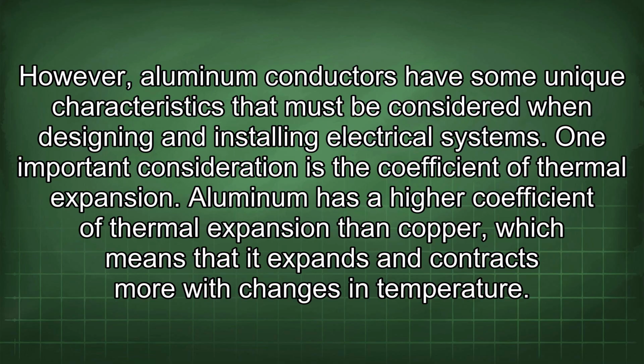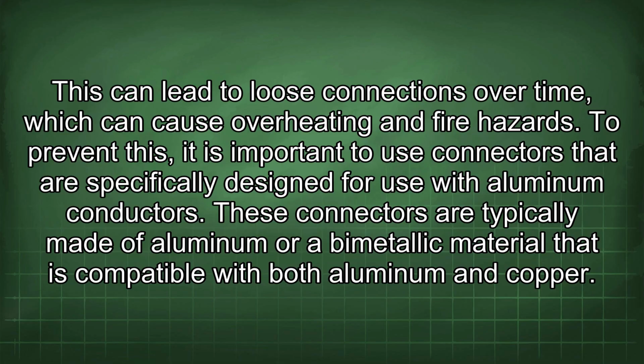One important consideration is the coefficient of thermal expansion. Aluminum has a higher coefficient of thermal expansion than copper, which means that it expands and contracts more with changes in temperature. This can lead to loose connections over time, which can cause overheating and fire hazards. To prevent this, it is important to use connectors that are specifically designed for use with aluminum conductors. These connectors are typically made of aluminum or a bimetallic material that is compatible with both aluminum and copper.